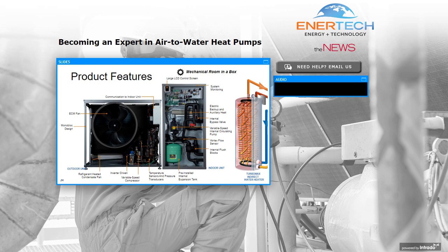The controls you see at the top are designed to interface directly with that outdoor unit. So there's a communication cable between the two pieces that gives us the ability to do outdoor temperature reset, to provide information about the outdoor unit on the screen. That's a touch screen, color screen on the indoor module. So having this package together is a huge labor saving, but it's also great for compatibility and the ability to add more features that you couldn't do with trying to source all these components separately.